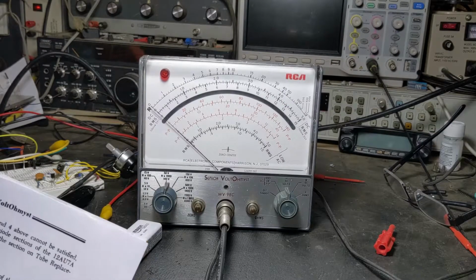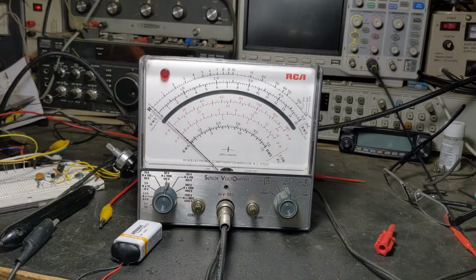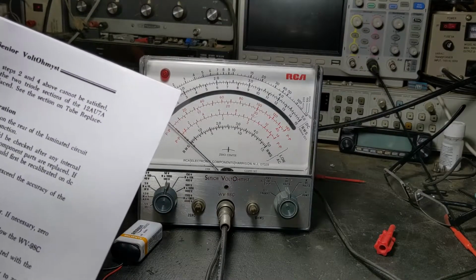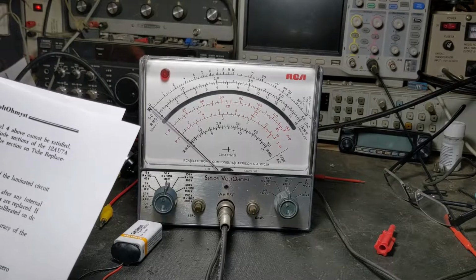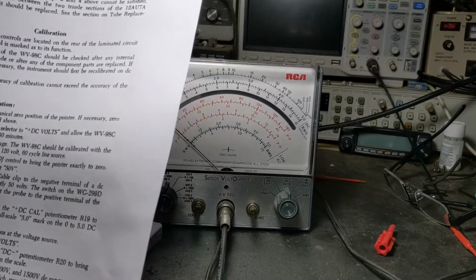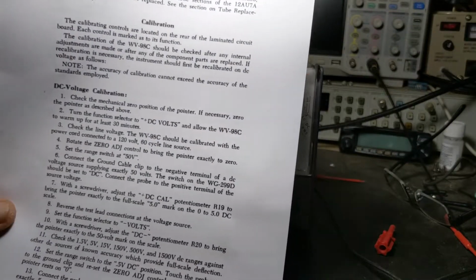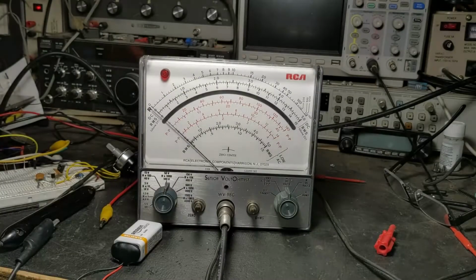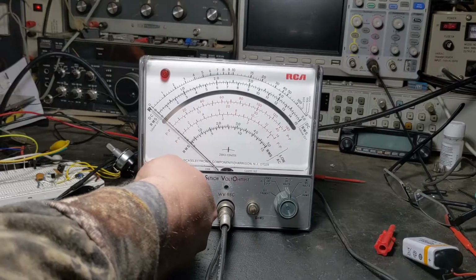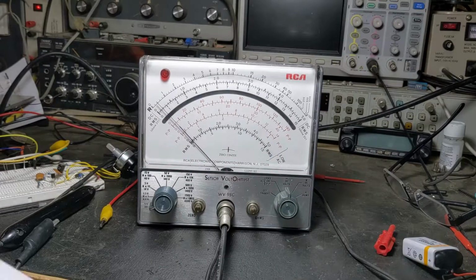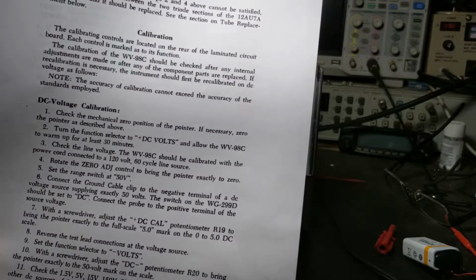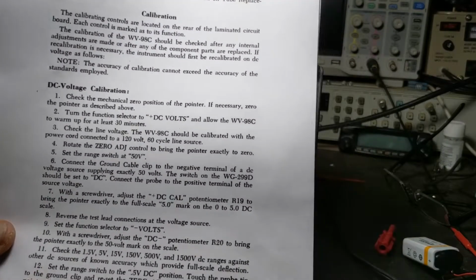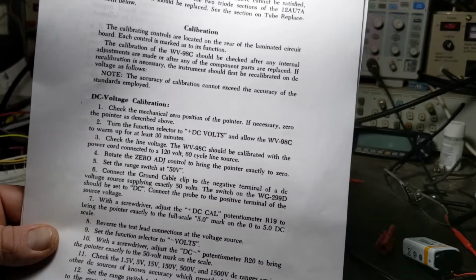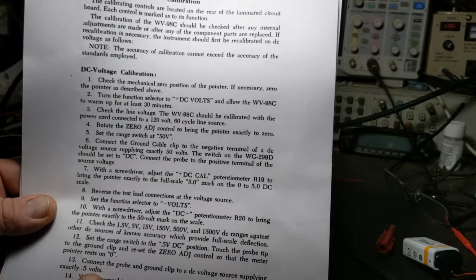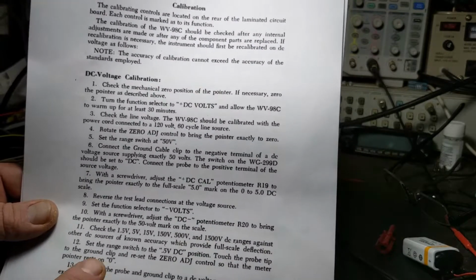I can go up to 500 volts, but no, actually, it just goes over 400 volts on my high voltage supply over there. So I wouldn't even be able to go all the way up without setting up some stuff in series or something. So anyway, then set the range switch to the 0.5 volts position. Okay, so we're going to come down here all the way down. Connect the probe and ground clip together. No, wait. Touch the probe tip to the ground clip and reset to 0. Adjust the control so that the pointer rests on 0. Then connect the probe and ground clip to a DC voltage source supplying 0.5 volts.